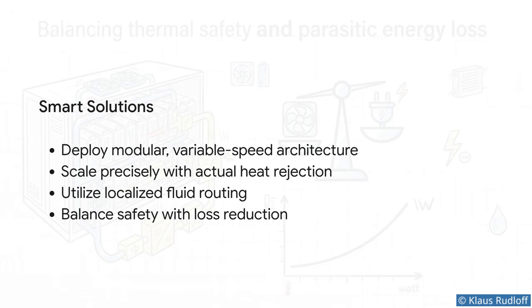Second, scale precisely with actual cell heat rejection — the system should only cool as much as the batteries are currently sweating, nothing more. Third, utilize localized fluid routing, directing cooling precisely to the hot spots in the battery racks rather than trying to freeze the entire container uniformly.